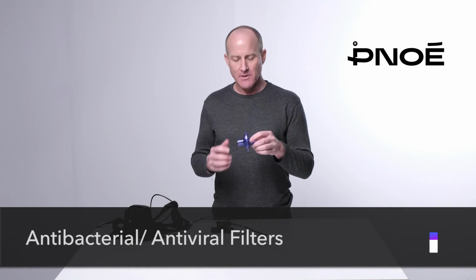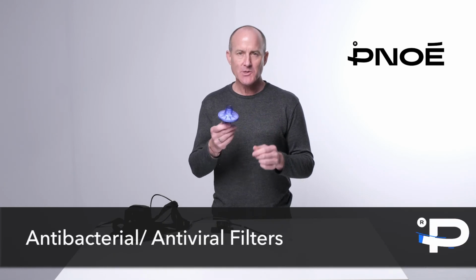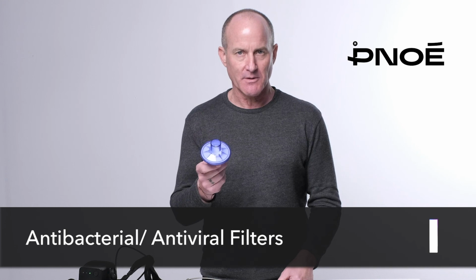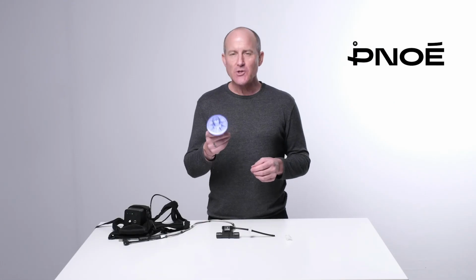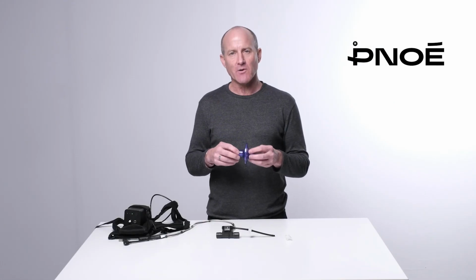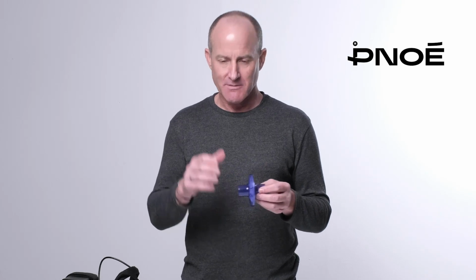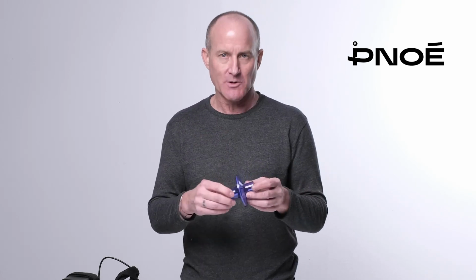For the antibacterial and antiviral filters, these are single use, single user, meaning that you can only use it on one person once and then it must be thrown out. If you choose to use antibacterial and antiviral filters on all your customers, meaning that if you're going to do 6 tests, you're going to use 6 different filters, then you only have to clean your flow sensor at the end of the day.